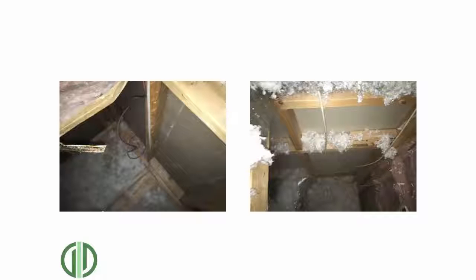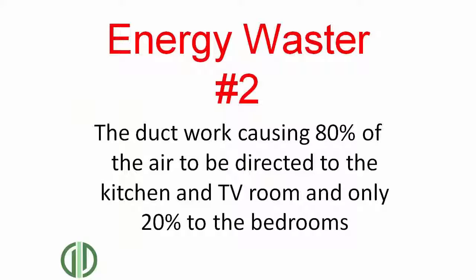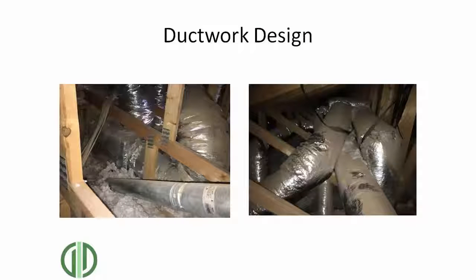The number 2 energy waster was that their ductwork was configured so 80% of the air was being directed in the kitchen and the TV room, and only 20% was going to the bedrooms, causing that hot room. Here's 2 photos of their ductwork, and they had their furnace in the garage and their ductwork went straight up into a mixing box, and then they had a second mixing box further down their vaulted ceiling, and these lines would go to the master bedroom.